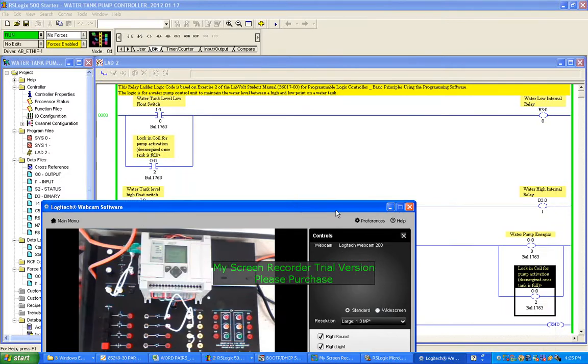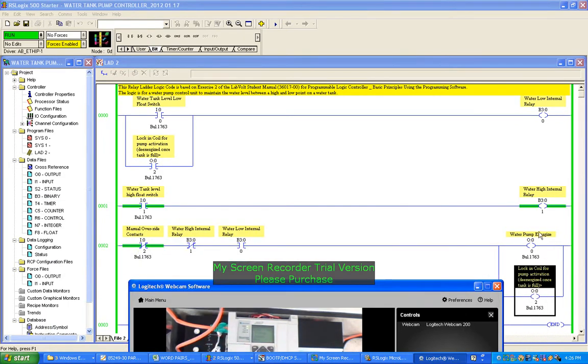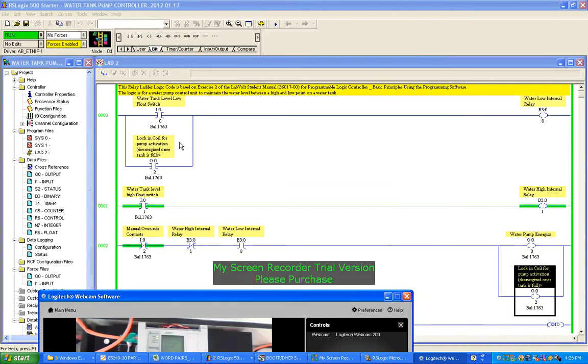So first thing, pump's off. Water's too low. Switch on low level water. Pump's turning on. After a period of time, the low level switch is switched back to off again, but that lock-in coil holds that circuit on, so it's holding the water pump on. Now, eventually it gets to the point where the tank is full.